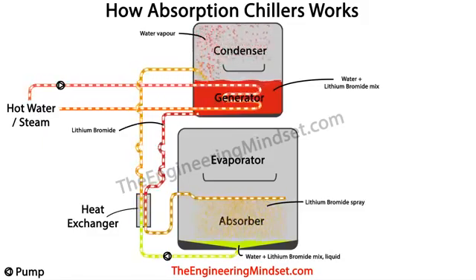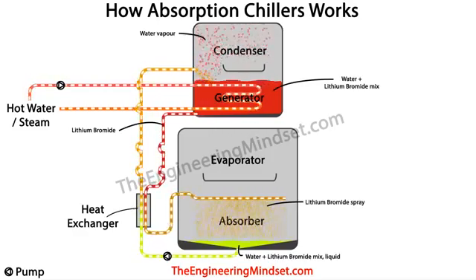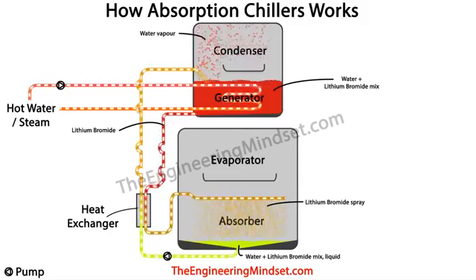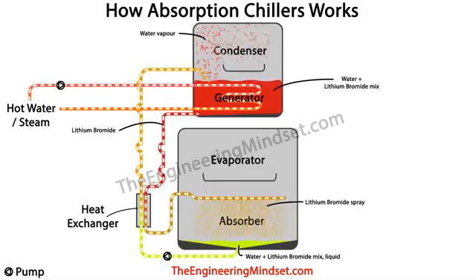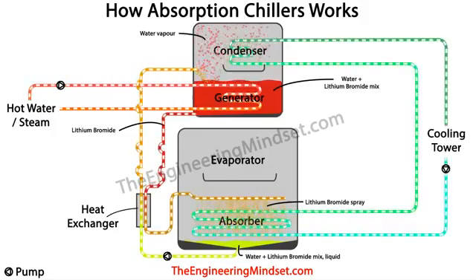Once the concentrated lithium bromide liquid has cooled down, it makes its way to the absorber where it is sprayed onto the chamber and will mix with the water before again being pumped to the generator to repeat the loop. But we will look at this part in more detail in just a minute.